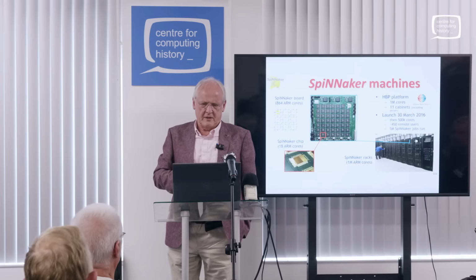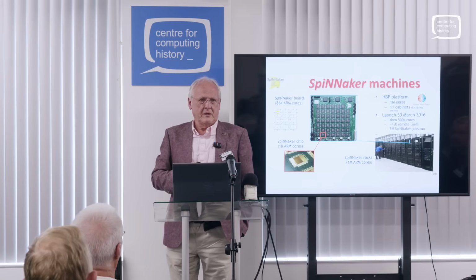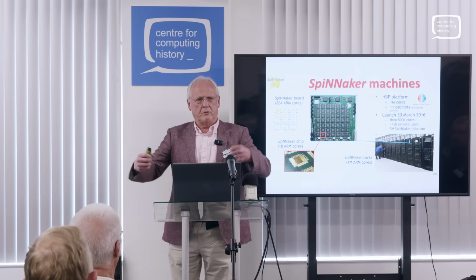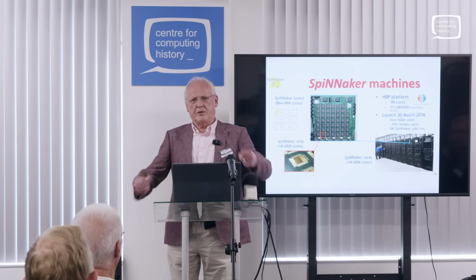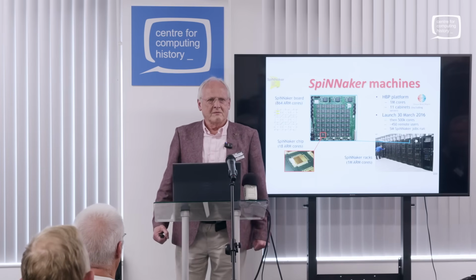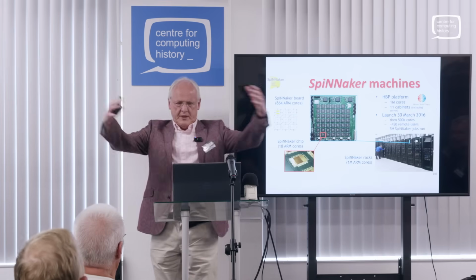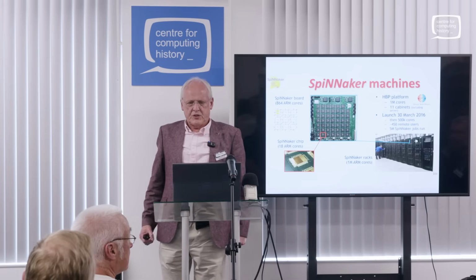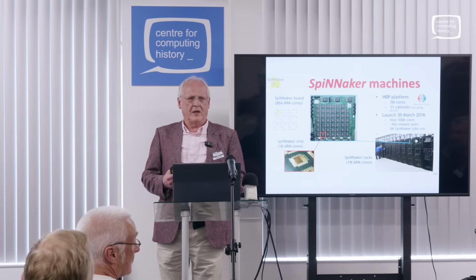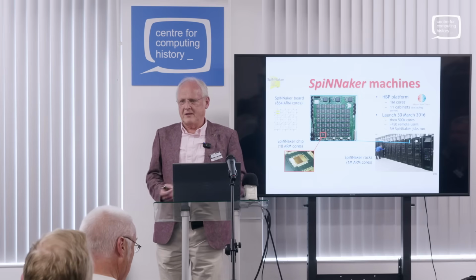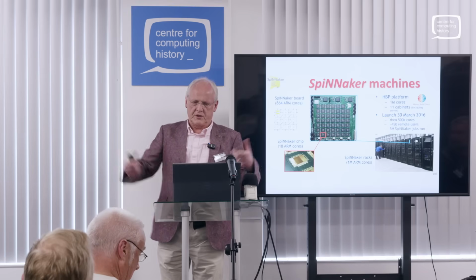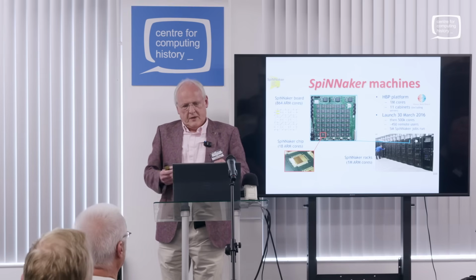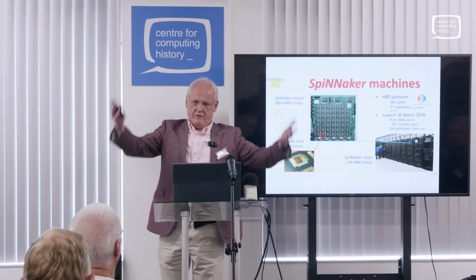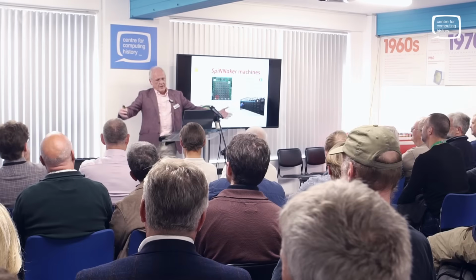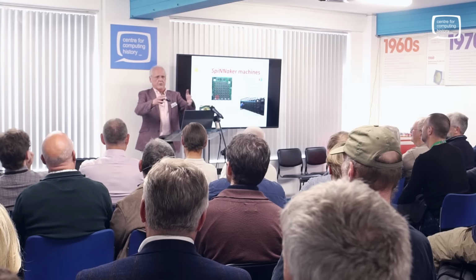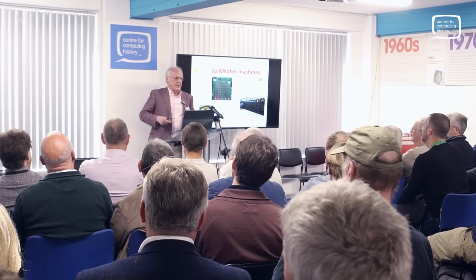The Kilburn building was a purpose-built computer building, back when computers were real computers. MU5 was a 128 kilowatt machine, so it has this plant room with big coolers, and chilled water is a kind of utility like electricity and gas. The SpiNNaker room has a chilled water supply that comes into chillers, and the air from the SpiNNaker machine gets taken out, runs through the chillers where it's chilled, and is blown back into the room, then sucked through the machine again. It's a closed air cooling system.